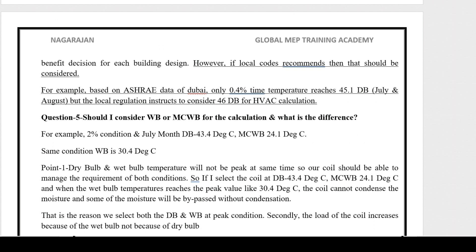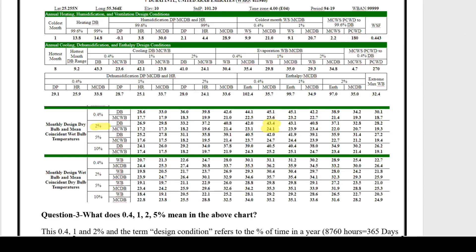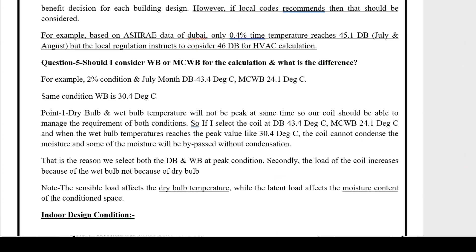Question five: should I consider the design wet bulb or mean coincident wet bulb for the calculation? At 2% for the hottest month, July, the dry bulb is 43.4°C and the mean coincident wet bulb is 24.1°C. But the monthly design wet bulb at the same 2% is 30.4°C — higher than the mean coincident wet bulb. The dry bulb and wet bulb temperatures will not peak at the same time, so the coil should be able to manage the requirements of both conditions.